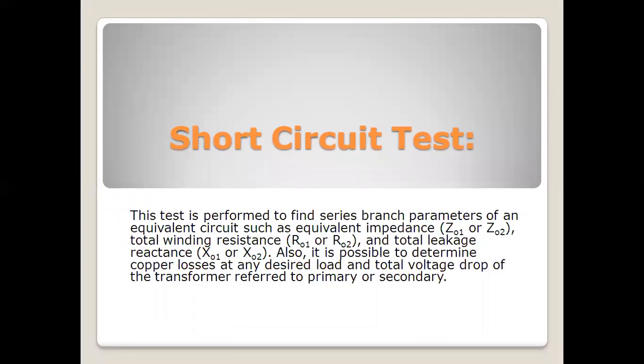Another is the short circuit test. The short circuit test is carried out in order to find the equivalent resistance and leakage reactance of the transformer. It is clear that the short circuit test is performed on the high voltage side of the transformer, and the low voltage side of the transformer is short circuited.